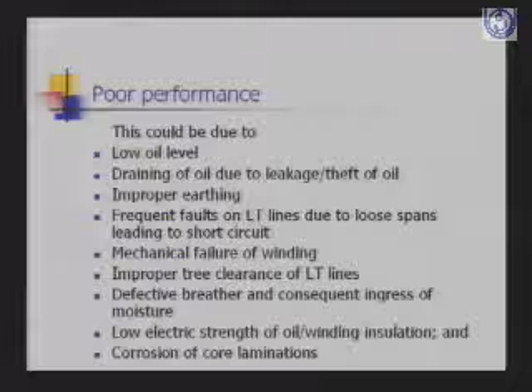You should do pre-cutting (tree trimming) along the LT line so that there is no fault on the LT lines which causes the transformer to fail. You should see the color of the silica gel in the breather. If there is moisture ingress in the transformer, then also it will fail, so you should see that there is no ingress of moisture, and if there is, take steps to reduce it. You should also see that there are no loose spans on the LT line, so that a failure on the LT line is not reflected on the transformer.